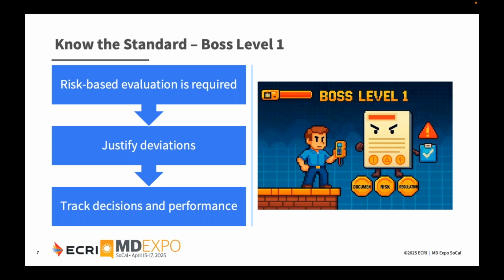Say, at one organization that I love, I came in and needed to understand why we were doing anesthesia machines twice as frequently. It had been determined, not necessarily through a risk-based assessment, but by a gut feeling before AEM, that doing the same step, no adjustment, same procedure, twice as frequently as the manufacturer would see an improvement. And they already had enough evidence to prove that it improved the longevity of those ventilators and reduced the number of calls your OR tech gets about anesthesia machines not working quite right. They reduced those to almost zero. So you can change the frequency. More frequent, less frequent, AEM.